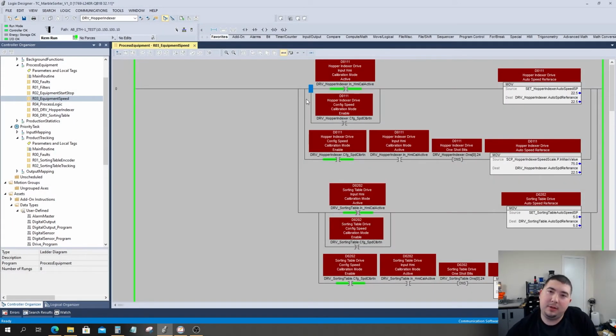So there's a couple different ways that you can do speed calibration on a given motor. One way would be to run the motor at a known speed and check it with a device known as a tachometer. However, in my case, I don't have a tachometer at this time. I plan on getting one a little bit later, but since we have physical hardware that can actually monitor our speed for us, we can essentially turn the machine into a tachometer of its own. So in order to do this, what we're going to be doing is tell the motors to run at a known speed, determine how fast it's rotating based on the input of the various devices, and then with that information we can determine our actual RPM value and adjust our speed control accordingly.